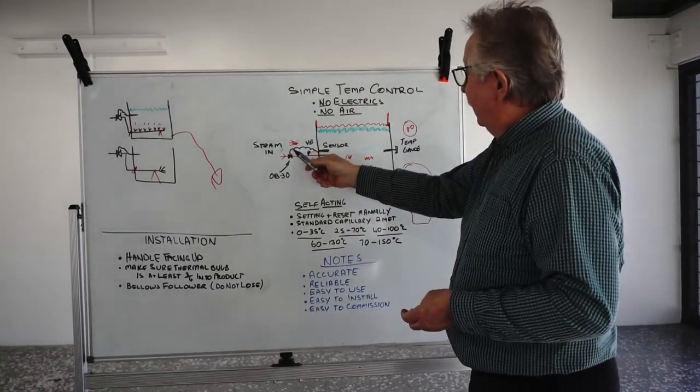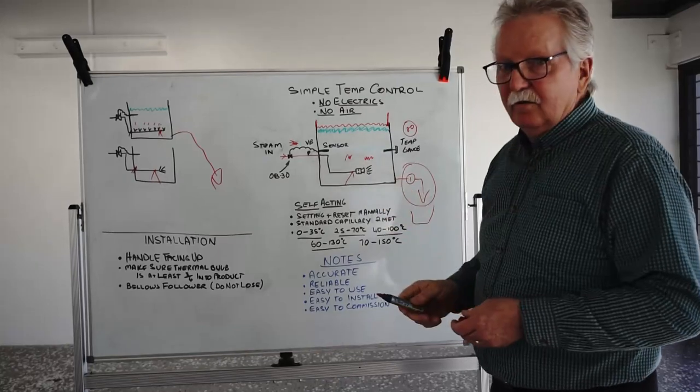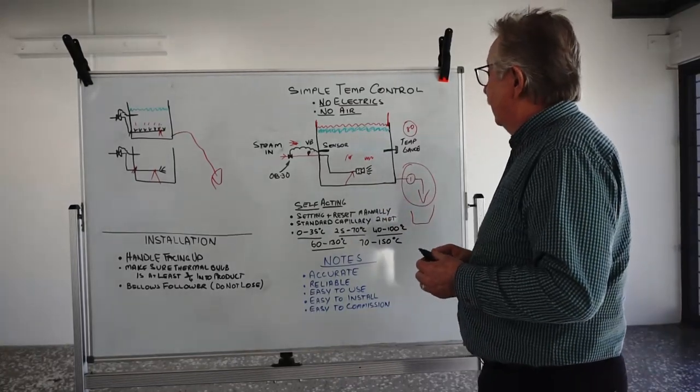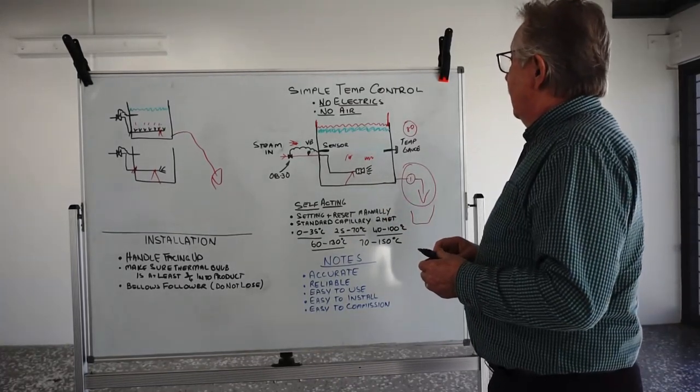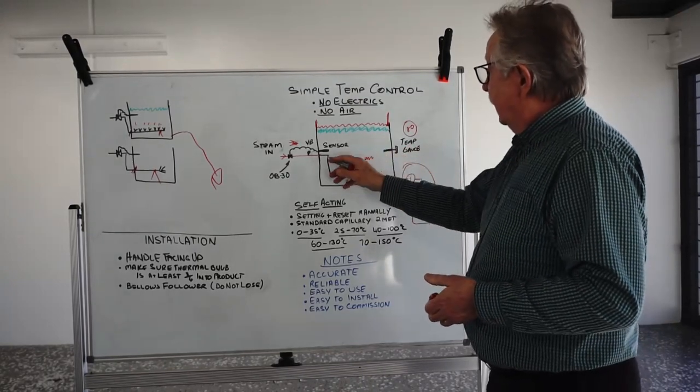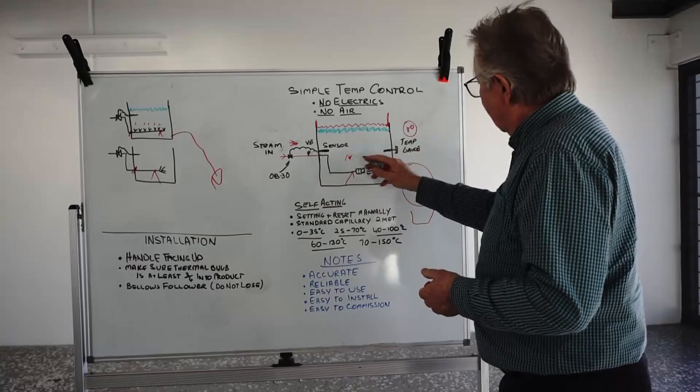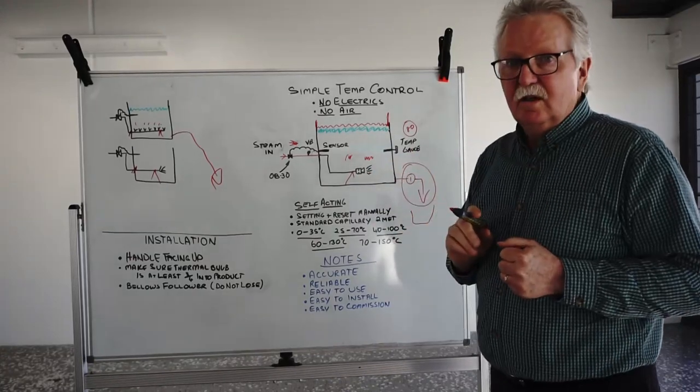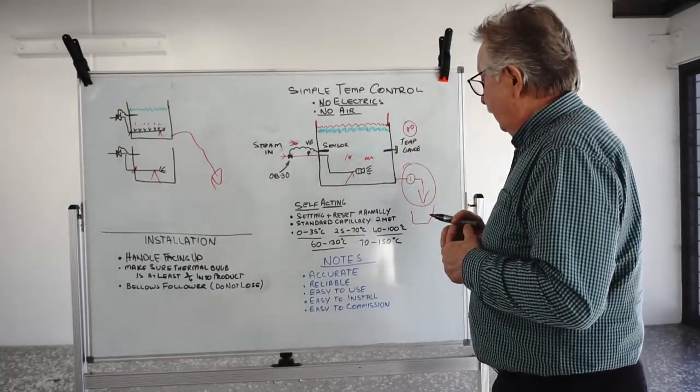Because there will be, for every kilogram of steam, there will be a litre of water end up inside that tank. Efficiency-wise, it'll be far more efficient than the coil because obviously all the energy is being used in heating up inside that tank.